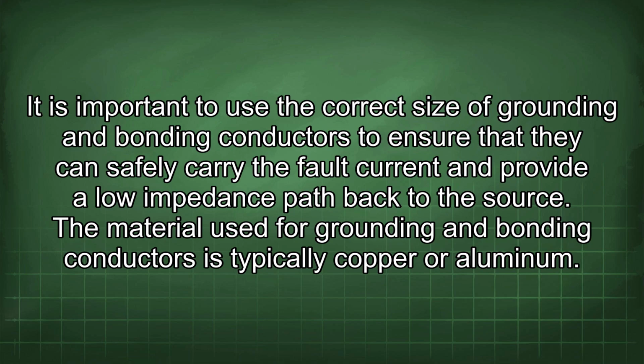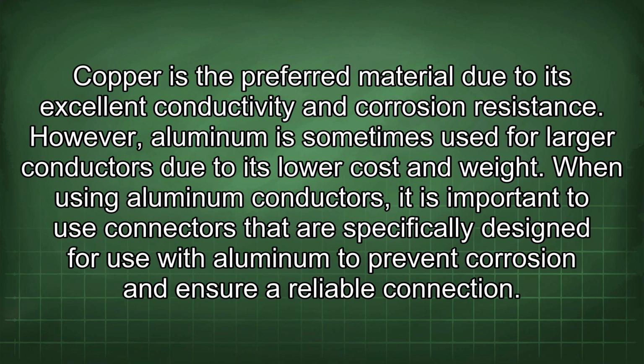The material used for grounding and bonding conductors is typically copper or aluminum. Copper is the preferred material due to its excellent conductivity and corrosion resistance. However, aluminum is sometimes used for larger conductors due to its low cost and weight. When using aluminum conductors, it is important to use connectors that are specifically designed for use with aluminum to prevent corrosion and ensure a reliable connection.